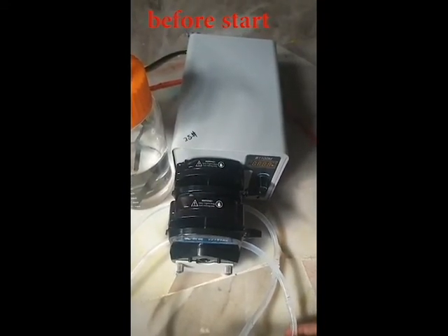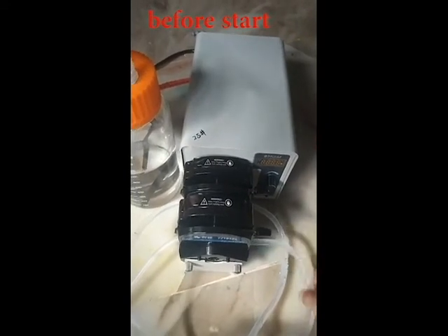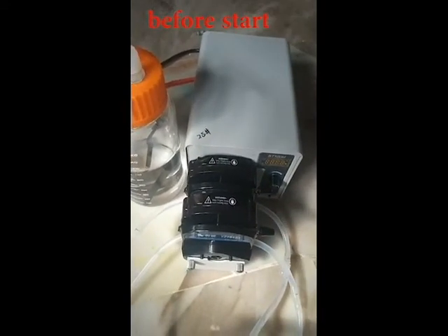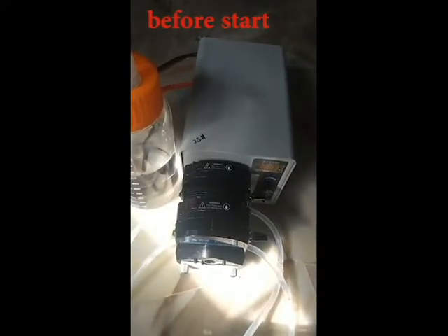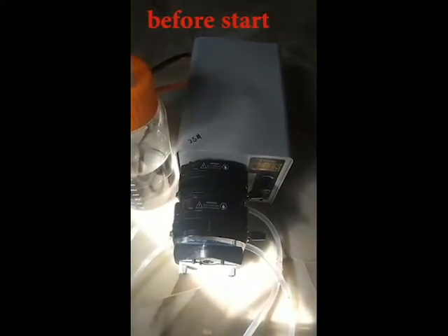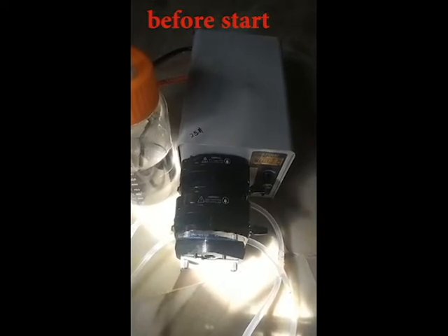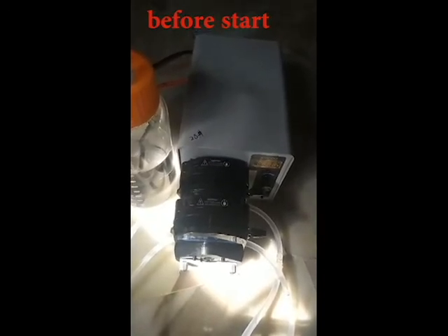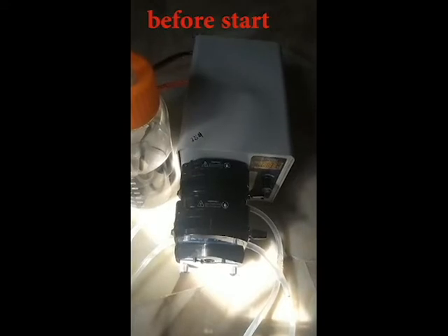And outside, we have chosen a Viton tube. Why are we not choosing a Viton tube here? Because a Viton tube can withstand highly corrosive chemicals like bromide. But if it's not really that corrosive, and another tube can withstand it, we will not choose Viton. Compared with other tubes, the disadvantage of Viton is its shorter life. So outside we are using a Viton tube, and for the one passing through the pump, we chose Tygon A16G for you.